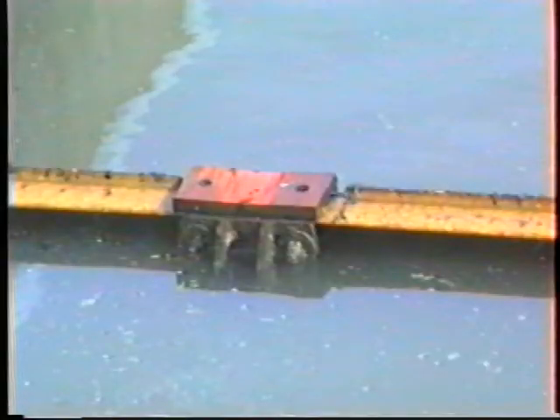In older clarifier units, you may even find metallic chains with redwood flights. Be sure to check the operation of the collection mechanism regularly. Observe the movement of the chain and scraper mechanism. It should be fairly smooth, not jerky. Be sure to look at and note the condition of the chain, wear shoes, and flights.